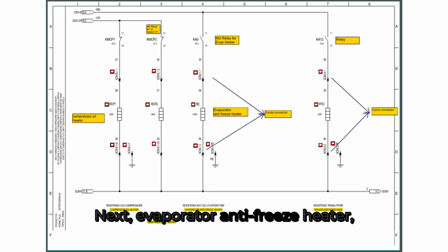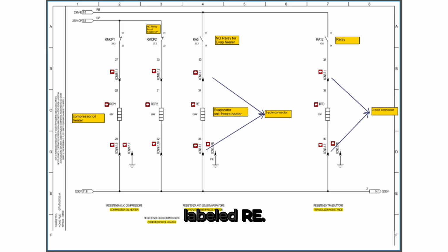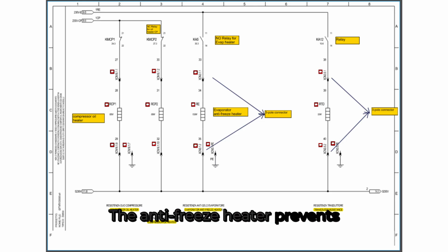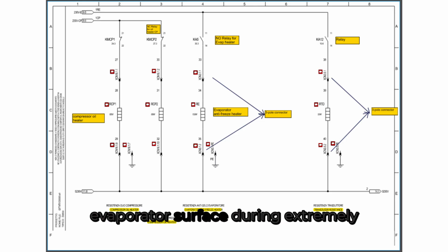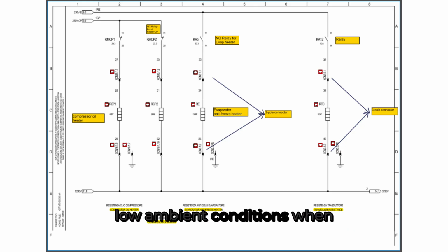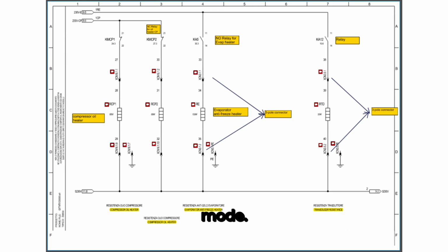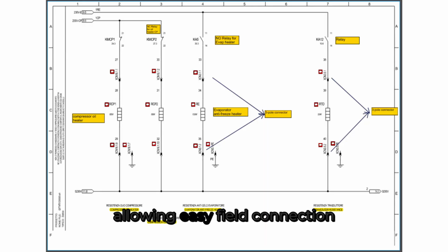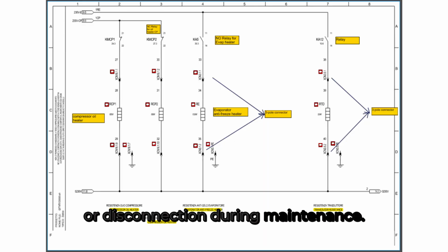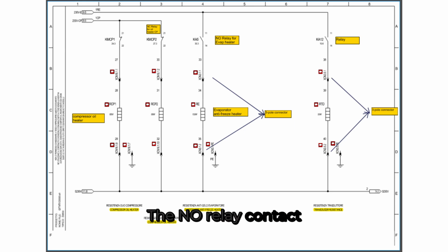Next, the evaporator antifreeze heater, labeled RE. This is a 150-watt heater connected through relay Ka5, which acts as its control point. The antifreeze heater prevents ice formation on the evaporator surface during extremely low ambient conditions when the heat pump is in standby or off mode. The power wiring passes through a 3-pole connector, allowing easy field connection or disconnection during maintenance. The NO relay contact Ka5 ensures that the heater energizes only when the control logic commands it.